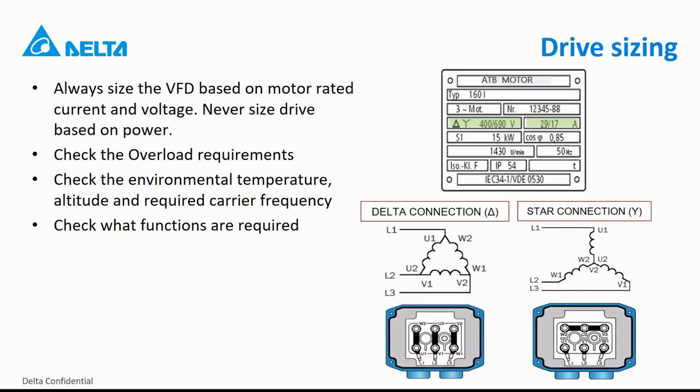Okay, so I got one request to do an example on carrier frequency. Let me open up the user manual. If we use, for instance, this motor here, I'll say that we choose a 400 volt drive, 29 amps. Let's say that this is a spindle motor application.